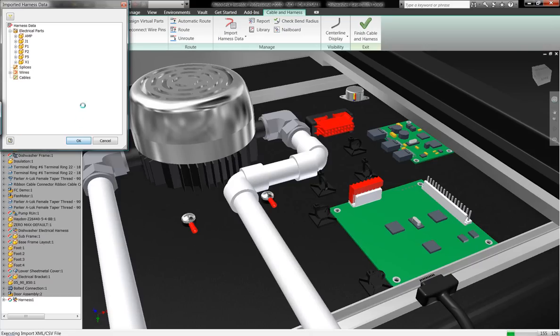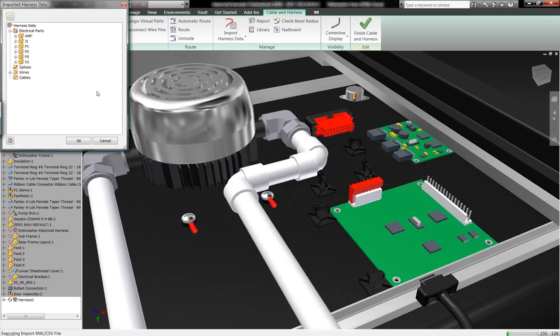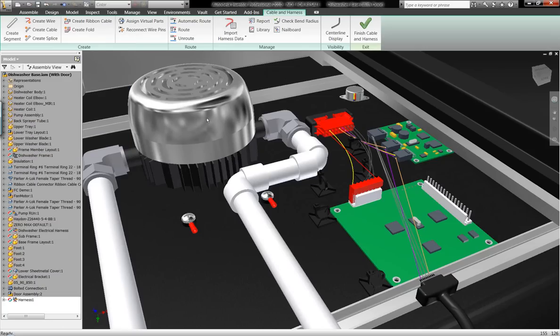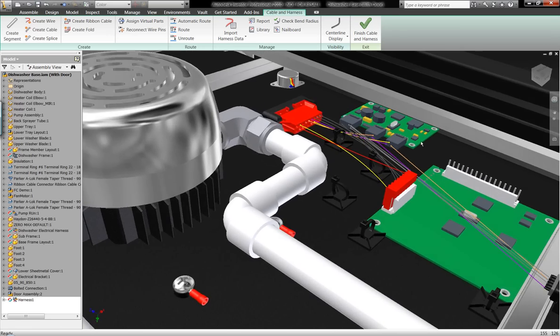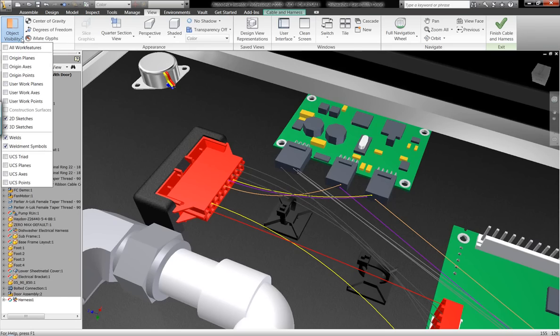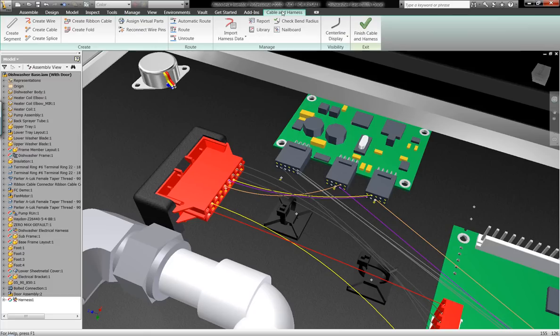Once I'm completed with that, I'm going to go ahead and import the data into Autodesk Inventor. So what we have on the AutoCAD Electrical side is the actual two-dimensional layouts of the geometry and we're importing those wires and connector information into our three-dimensional model. It's going to give us a visual, an actual visual representation of where these wires run from pin one on connector one to pin two on connector three, for example.